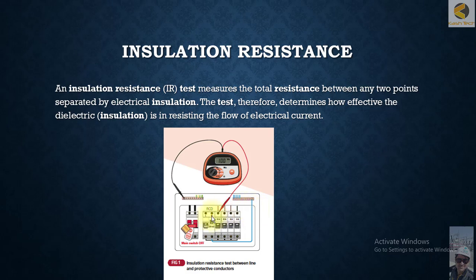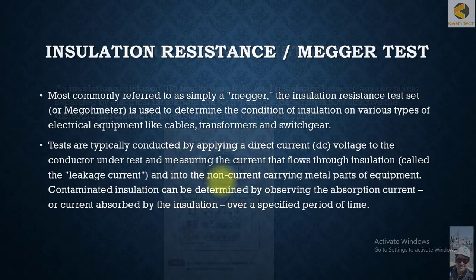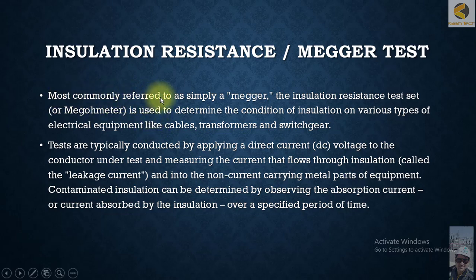Here you can see in a simple diagram: if you want to measure the insulation resistance for an MCB phase wiring, this is the grounding strip and the ground. These two points are isolated by electrical insulation. You connect the phase lead to the terminal and the black ground lead to ground, and it will show you the insulation resistance.